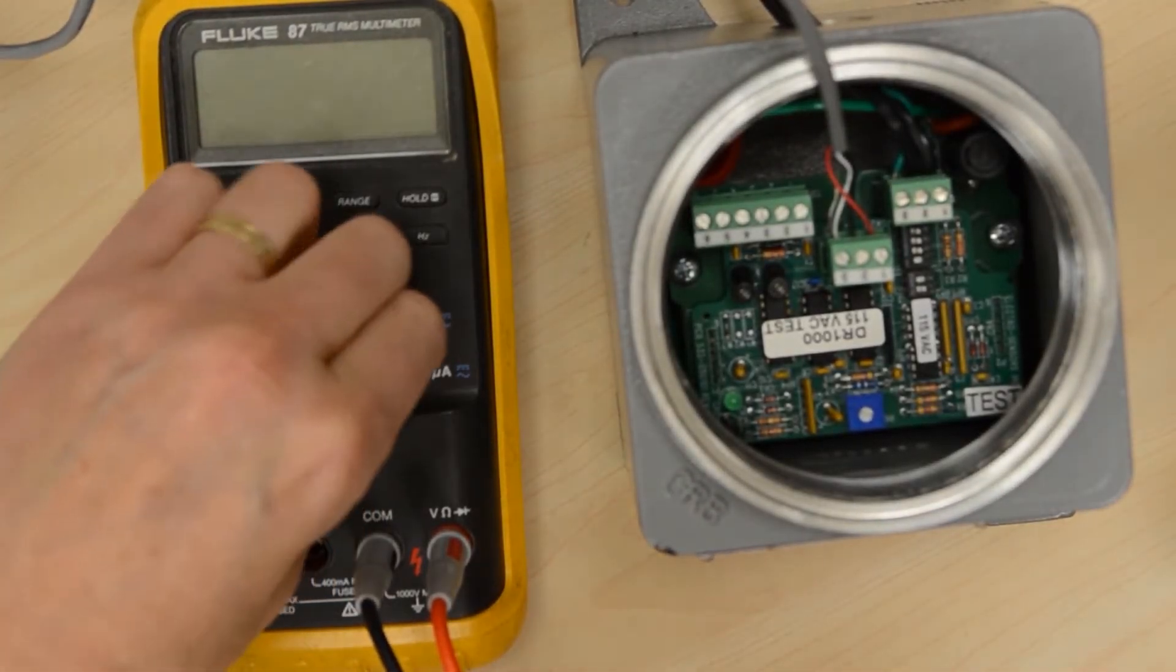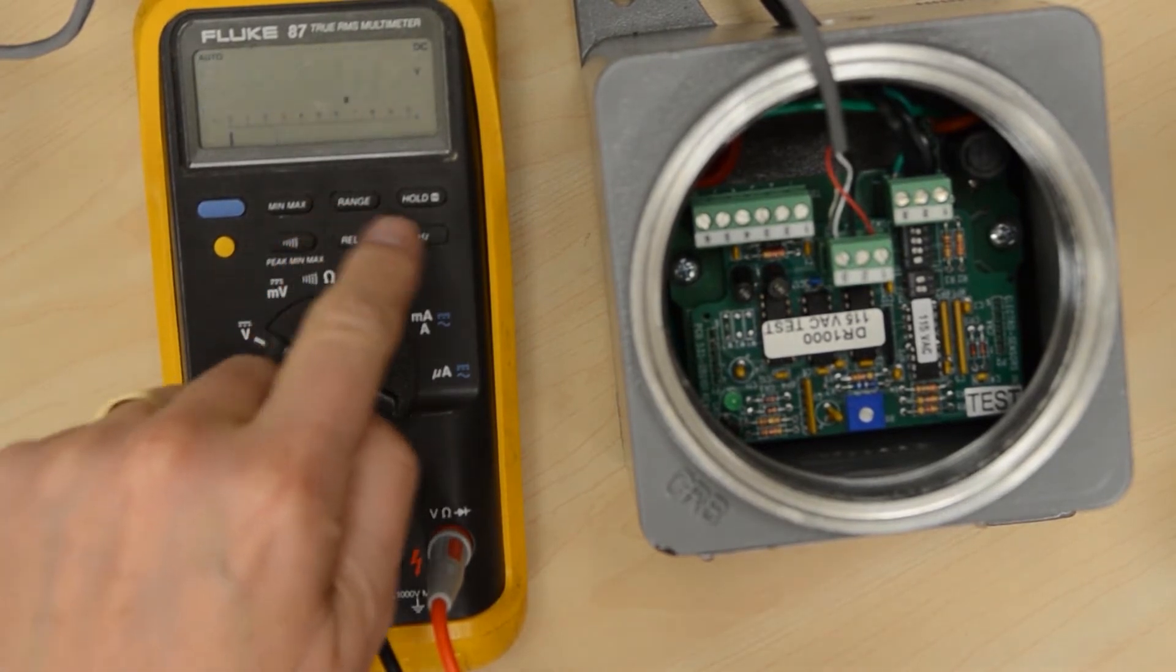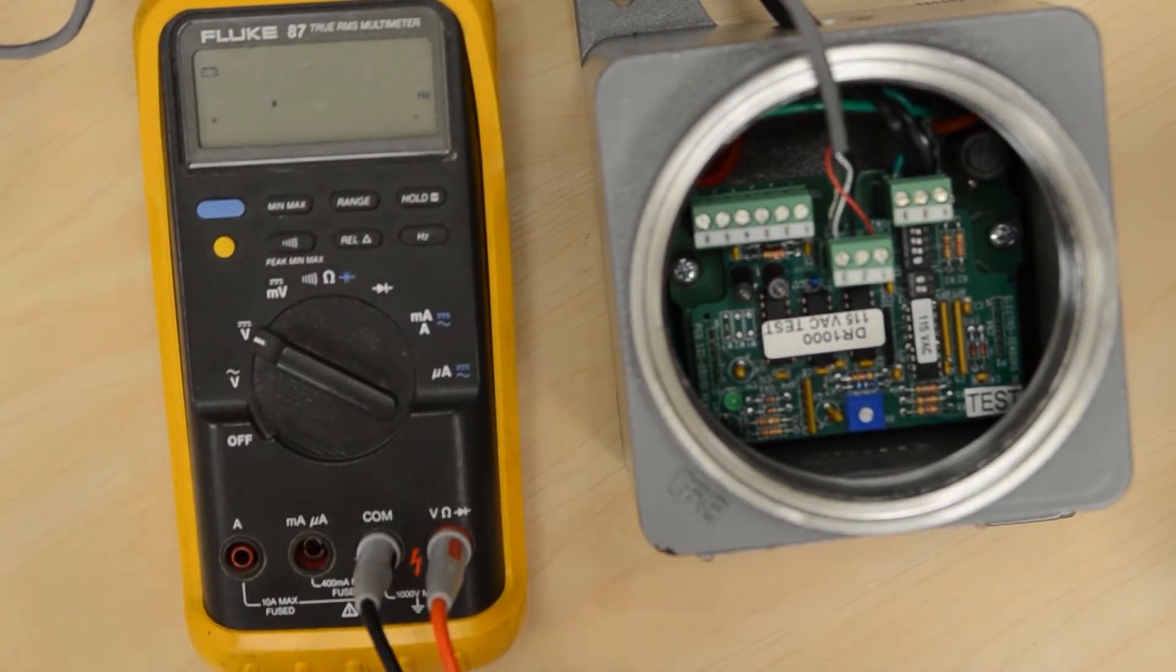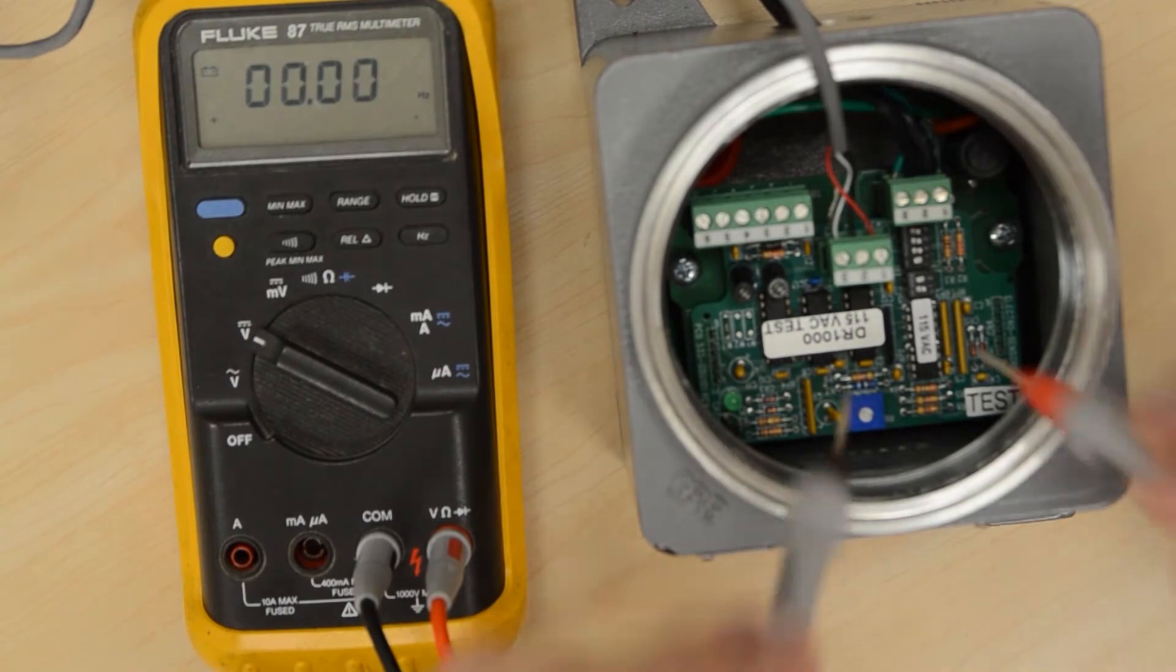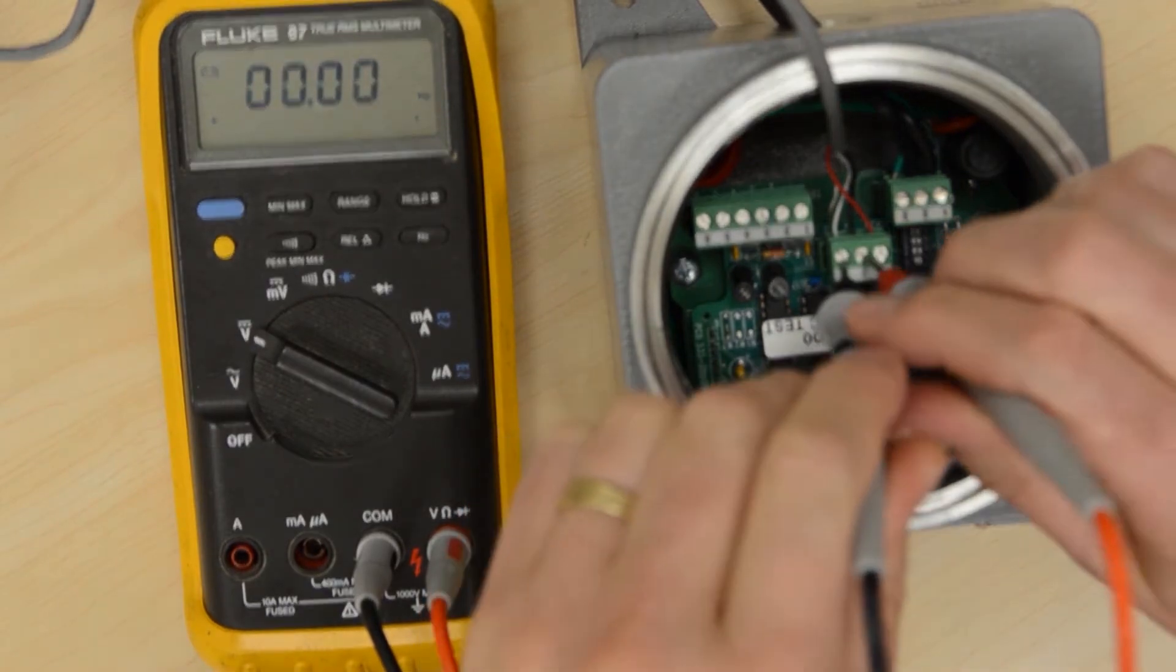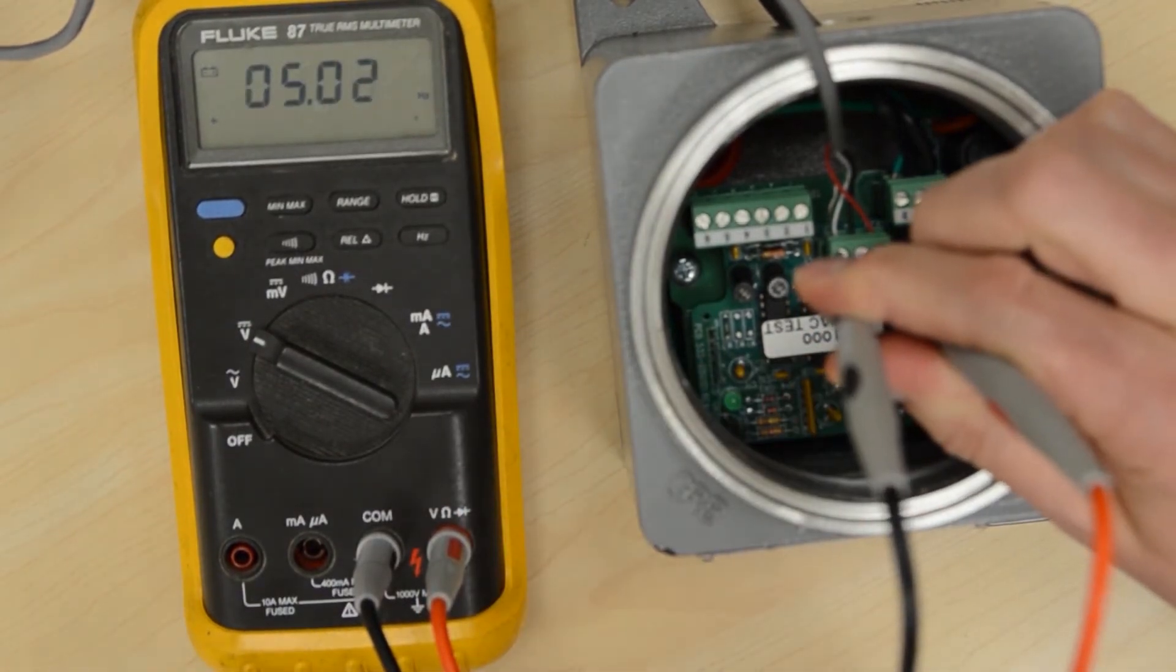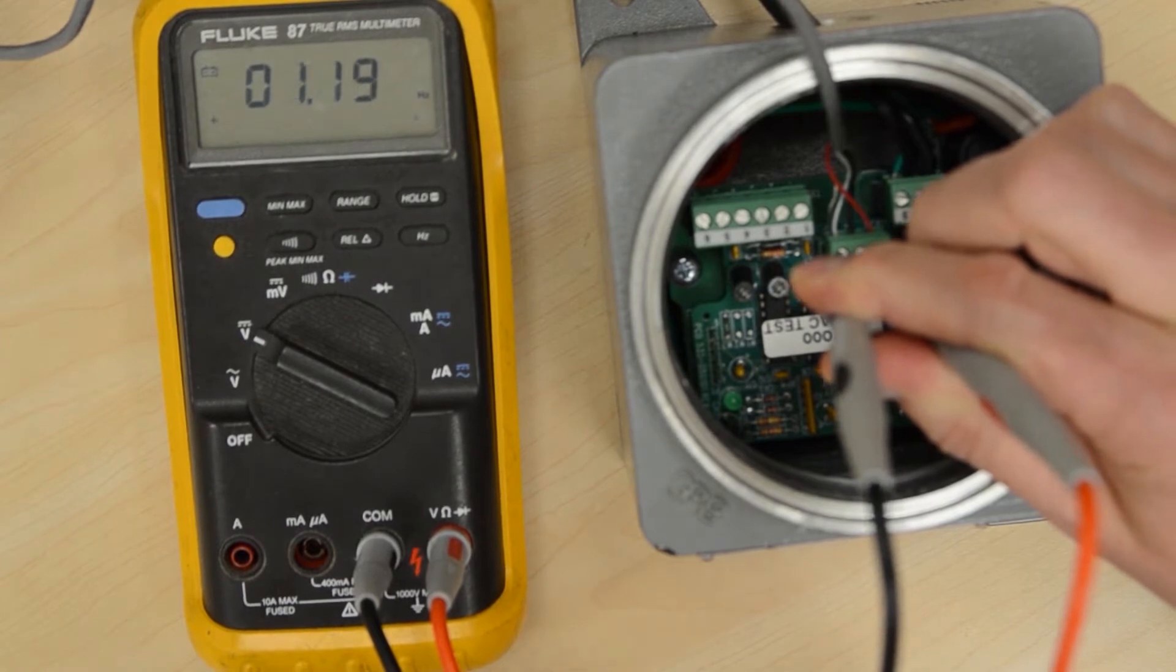When testing with a more advanced multimeter for frequency, you must place the meter in the Hertz mode and place the positive on TB2 pin 2 and the negative on TB2 pin 3. This will show the frequency.